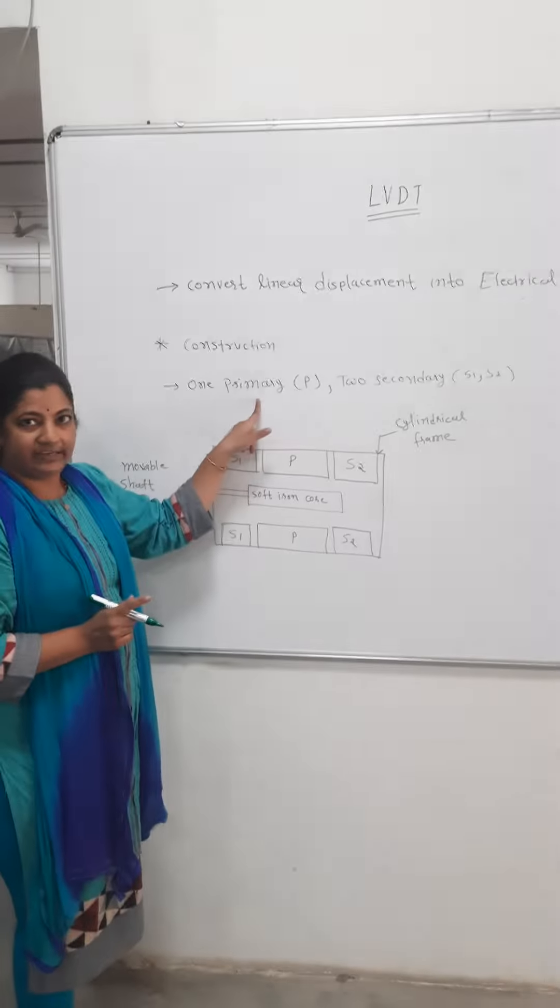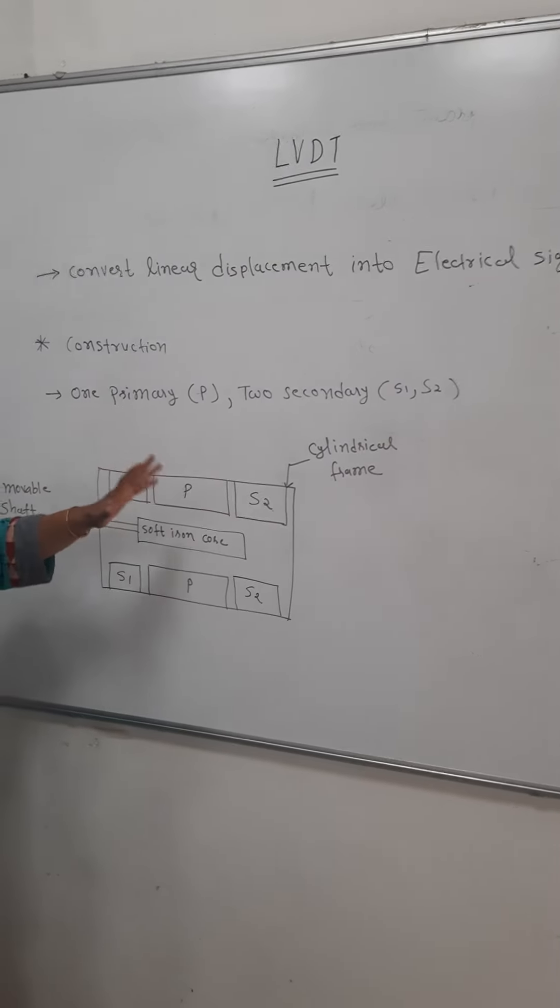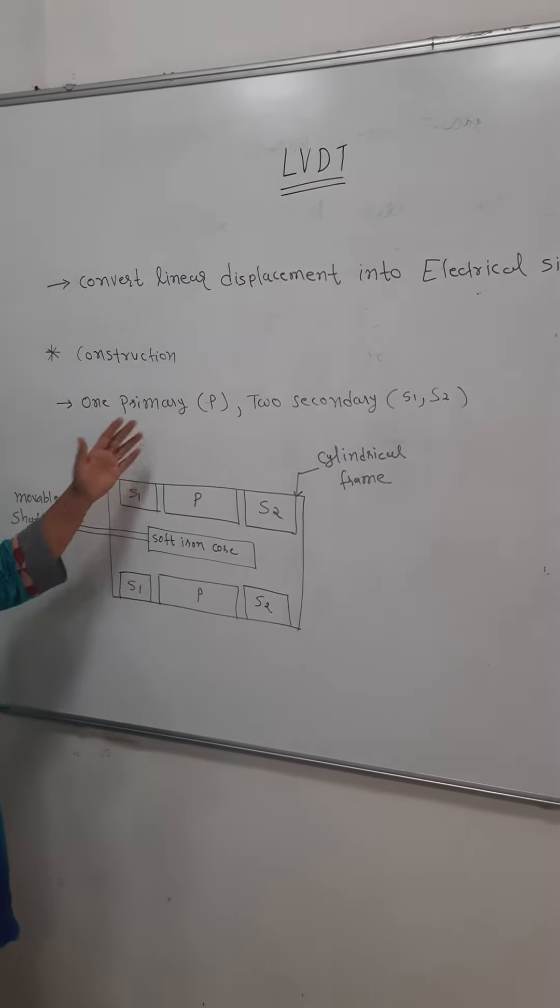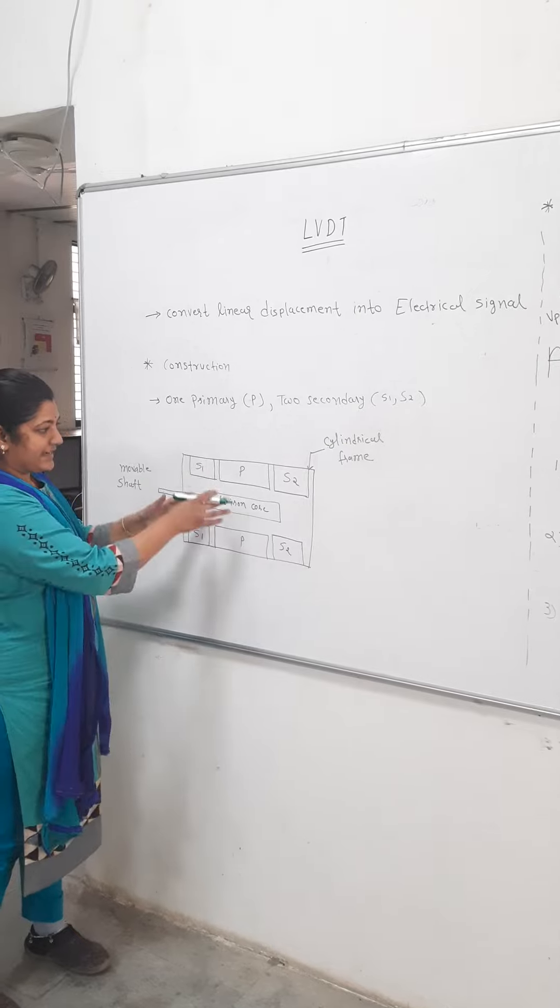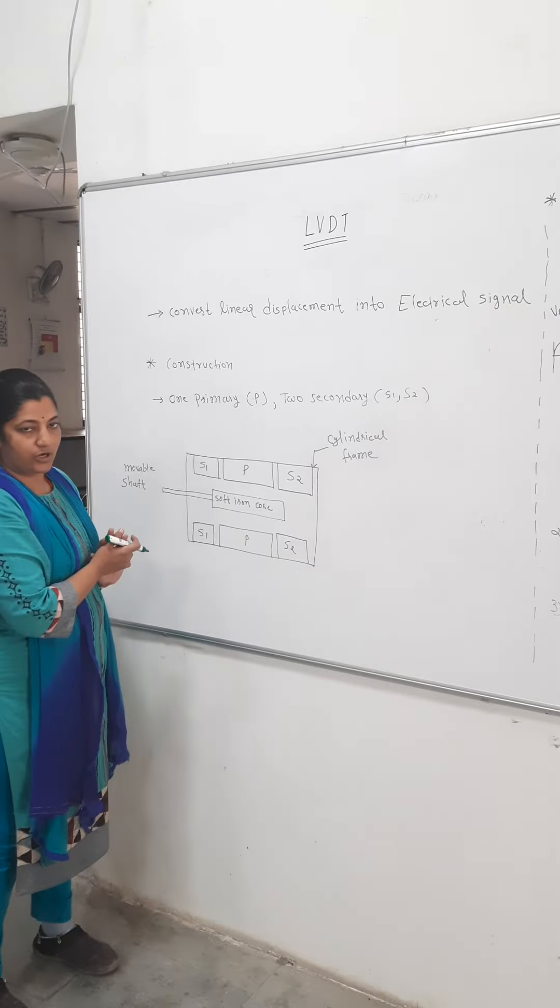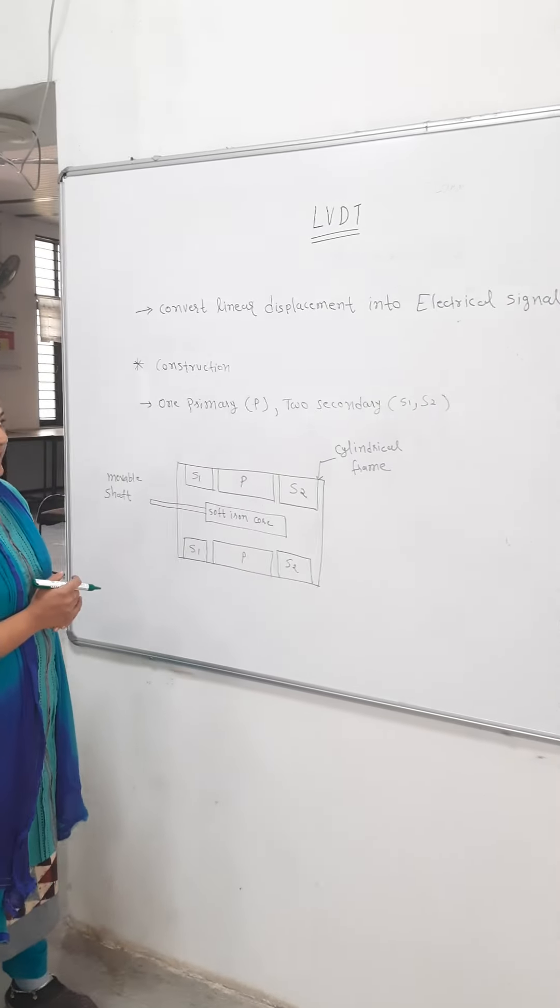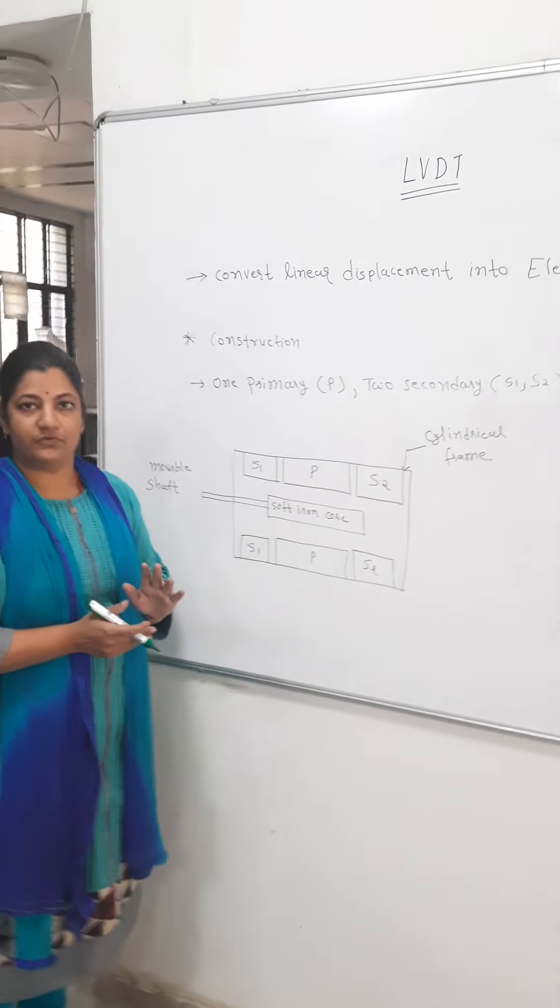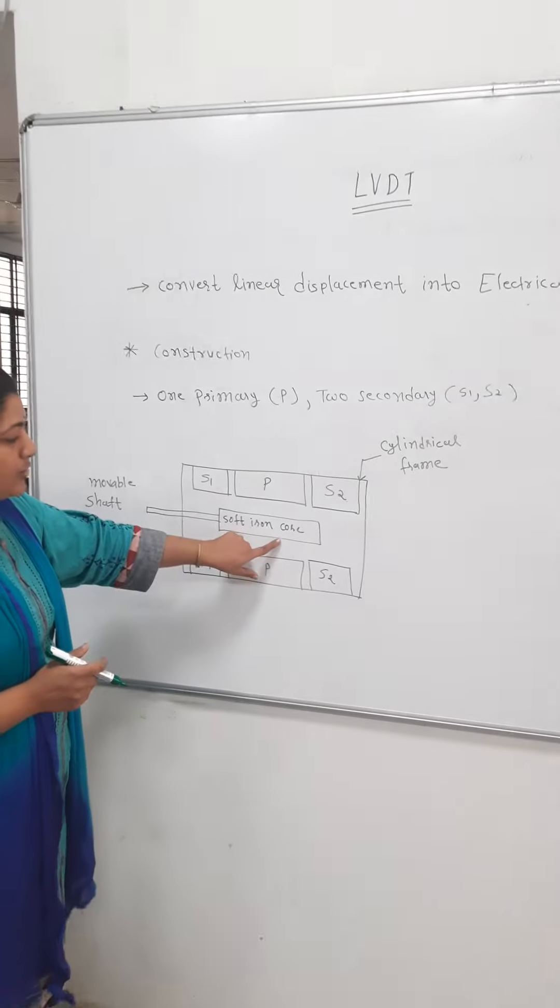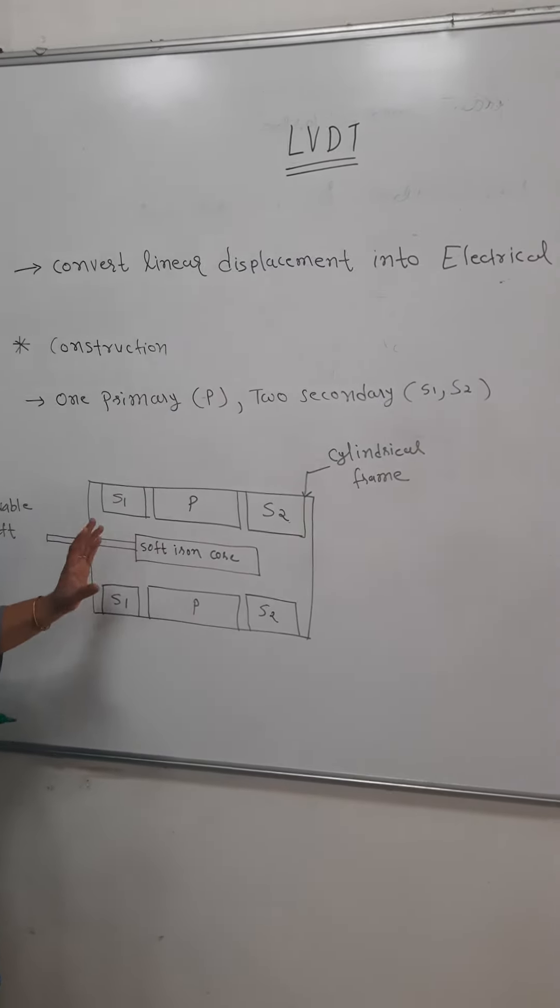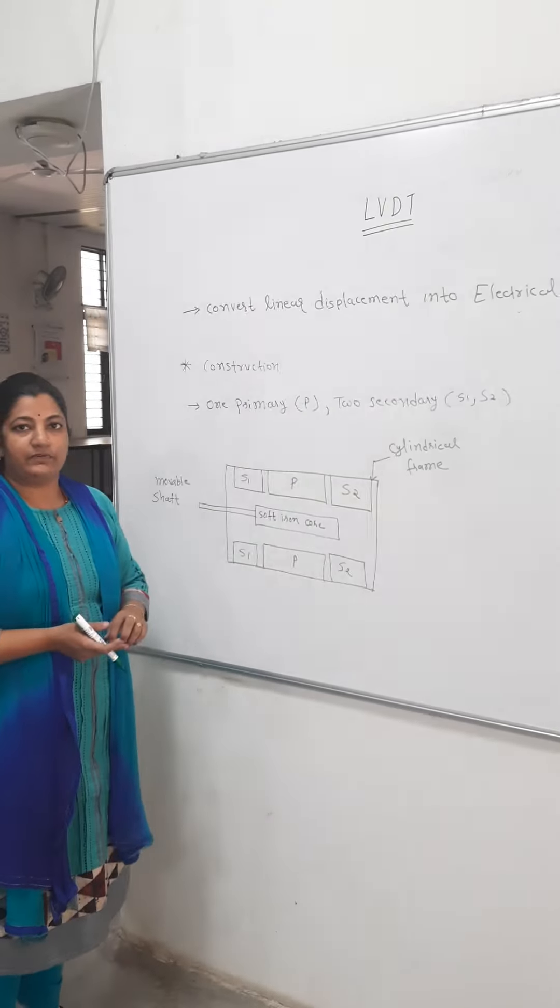First things, one primary it will have and two secondaries. So it is one kind of transformer but having one primary and two secondary. Same thing is given in the construction form also. You can see this is the cylindrical frame where inside we have to put all the components, primary and on both sides we have to place S1 and S2 in such a way that both have the same number of turns. Now, another side in between this we have the soft iron core which is movable in nature. So this motion we are trying to convert in the form of electrical signal that is the concept of LVDT.